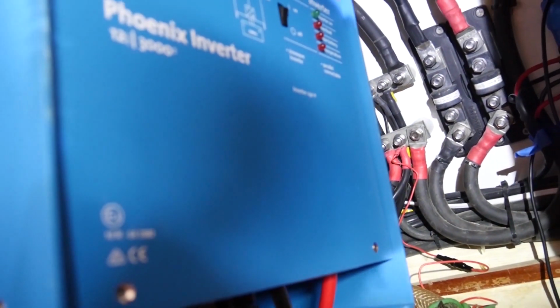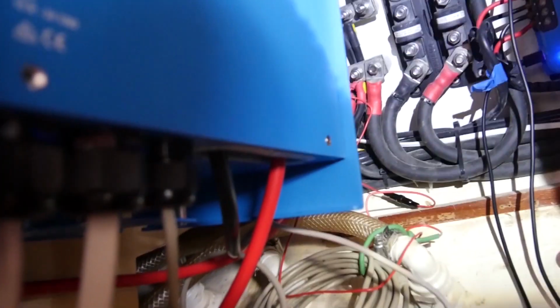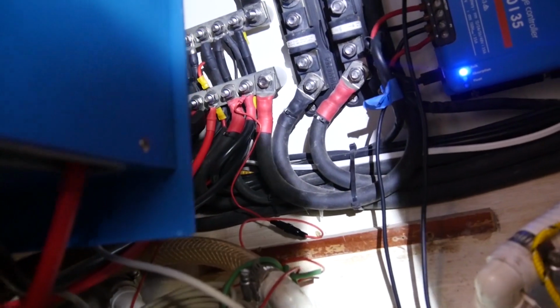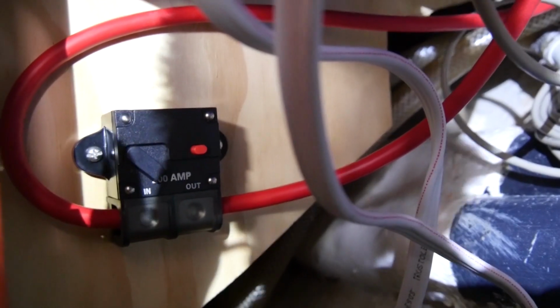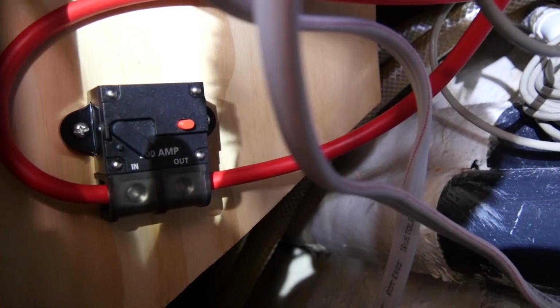So I need to take the back off the inverter, undo the cables in there. I've got to take them off the bars there, and I also need to cut the positive cable and put it into the circuit breaker here. I might flip the circuit breaker around so it's easier to get the cable in.